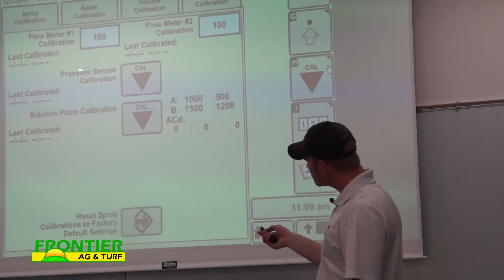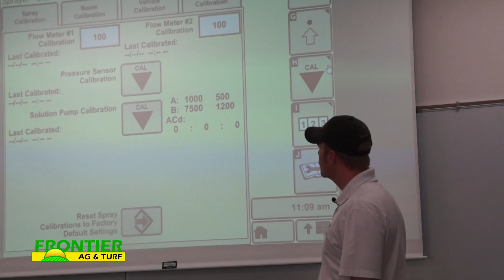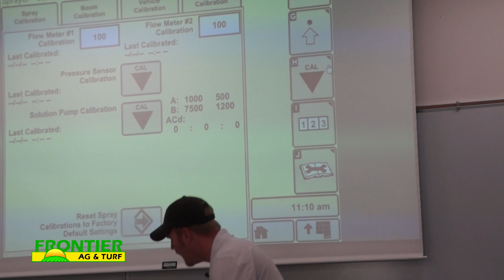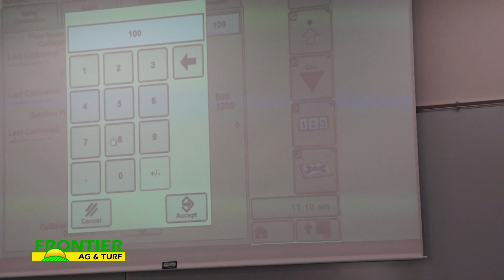It will timestamp them as well, so I know when the last time it actually was calibrated or looked at. So if you look at it after a month or so, just go back and recal it. Anytime you go back in here, say the calibration was 100, I would say it was actually 107, whatever. I accept. Now it timestamped it today and what time it actually did. If you got a high flow system, you got two cal numbers. Tell the difference. Flow meter 1 is the closest to the cab. Flow meter 2 is the farthest from the cab. So make sure you don't get them swapped because then your flows can change.